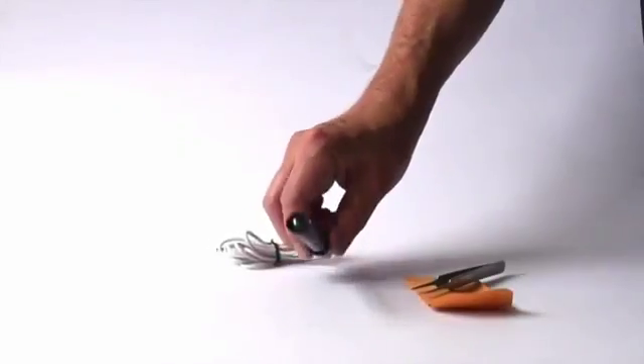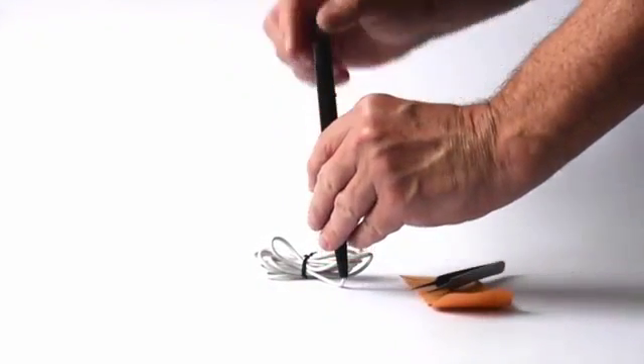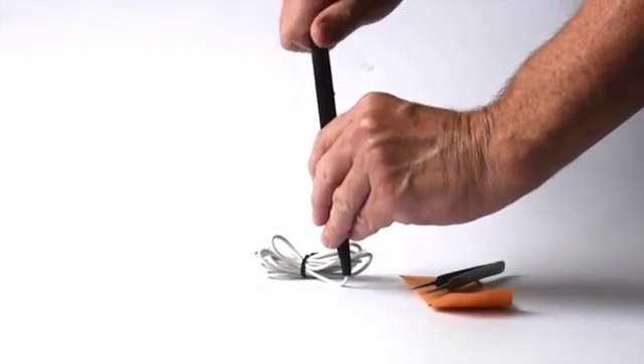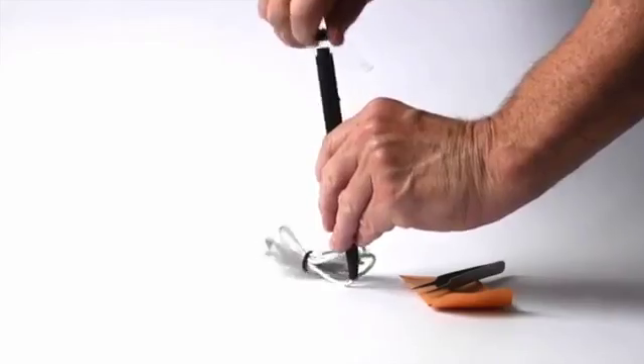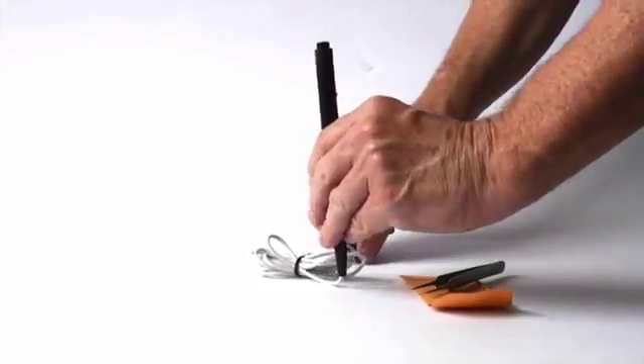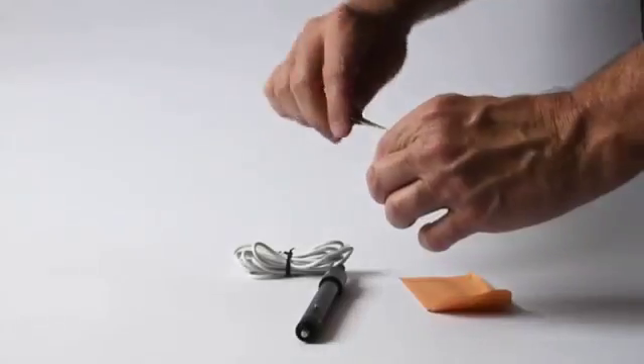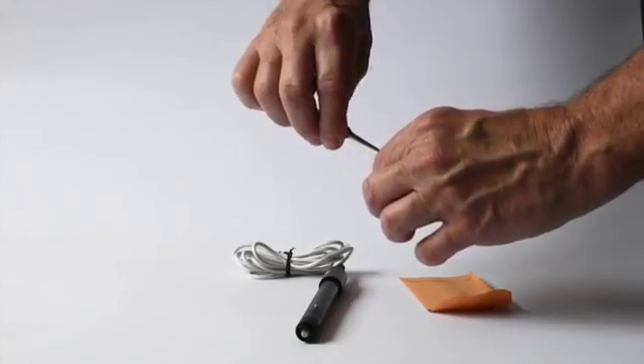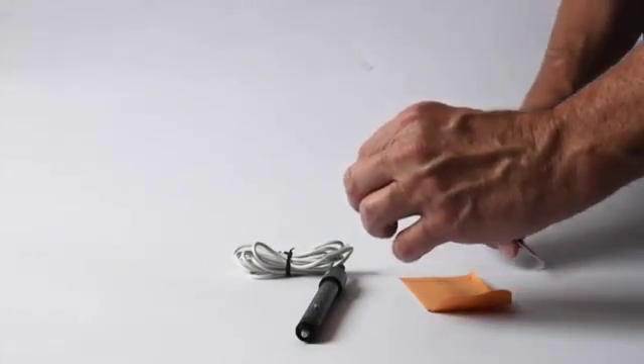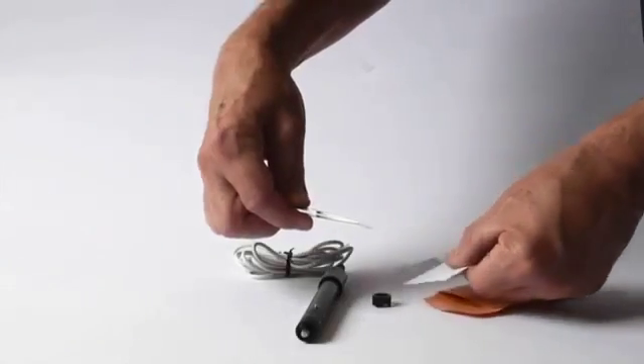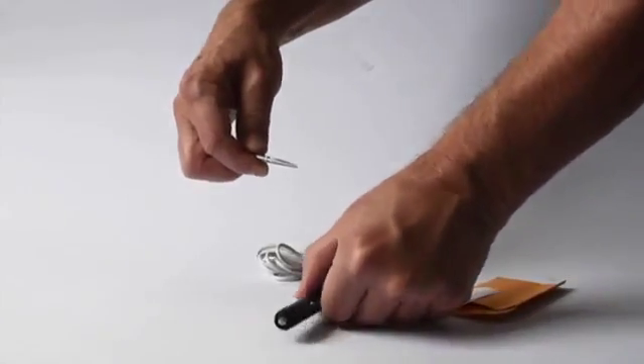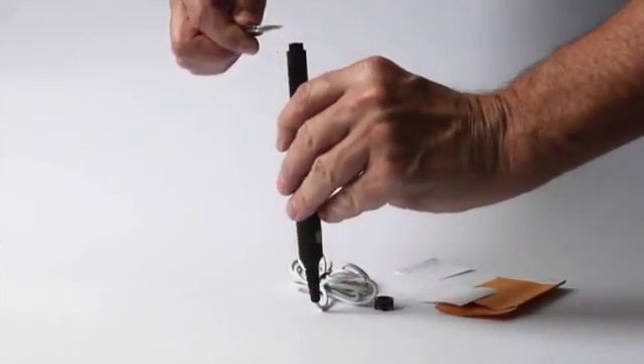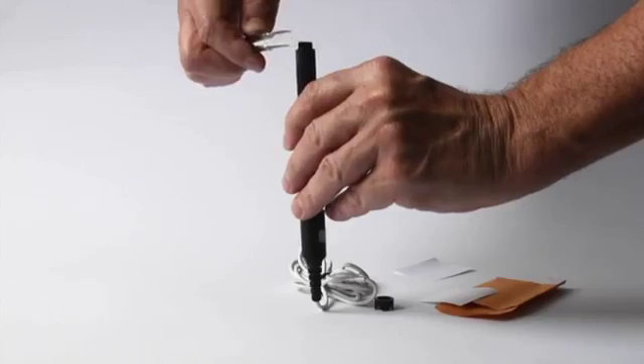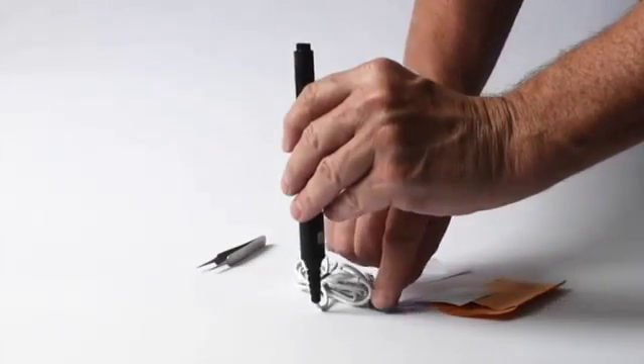If you start receiving inaccurate results from the sensor, try changing the membrane. To change the membrane, first unscrew the guard cap, remove the old membrane, lay the new membrane on the cap, the membrane should be stretched uniformly.